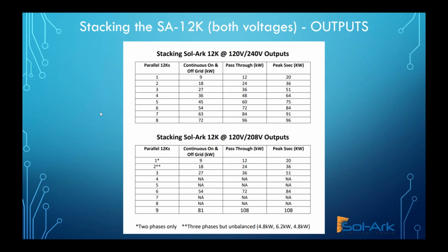Thank you, Dustin. One of my favorite applications for the 208 volt is a small pharmacy that would need to keep their medicine cold if the grid ever went down. Excellent application for 208 volt 3-phase. Again, you can stack up to 9 Sol-Arks, 81,000 continuous watts, 108,000 peak power. If you have 9 Sol-Arks, you could hook up 9 times 13, 117 kilowatts of PV directly into those 9 inverters, and you could hook up, I don't know, a dozen Fortress E-Vaults. That's going to get you over 200 kilowatt hours. So a very formidable system, very functional, very powerful, and really enables a lot of battery backup possibilities in commercial.